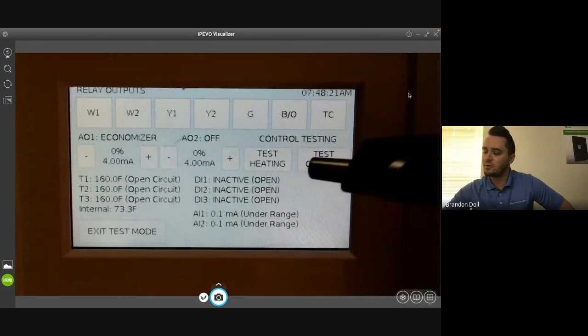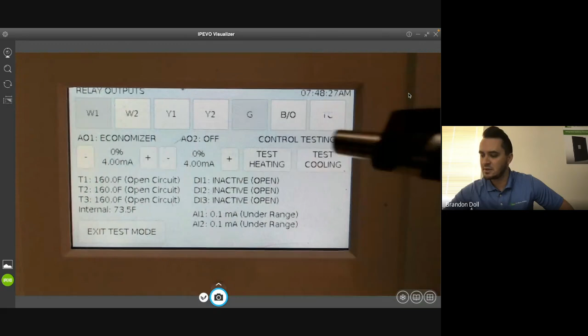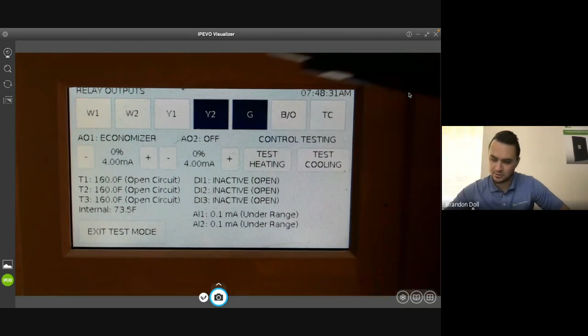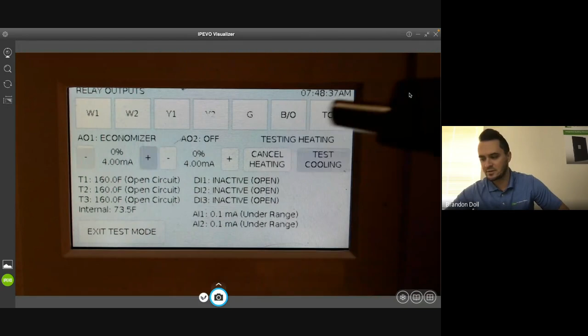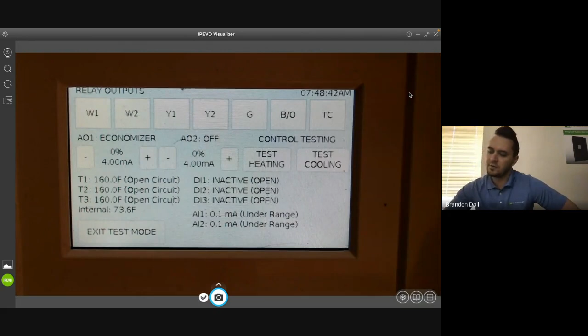So enter, and from right here you can test your heating, and it kicks on the W1 and fan for safety reasons. You can test your cooling, or test certain stages of heat too if you want. If you do the full heat testing and cool testing, that takes about 10 minutes and gives you feedback.